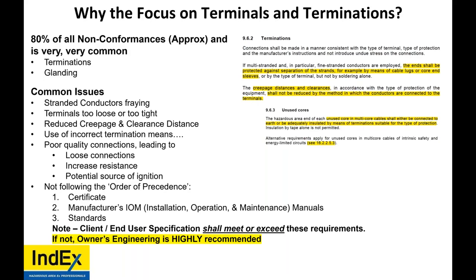So the importance of terminations is to stop line-to-line shorts, line-to-ground faults, and to not cause explosions by not having arcs, sparks, and hot points. Approximately 80% of all our non-conformances in our industry are glanding and terminations. Separating those two is very difficult because usually the faults go together.